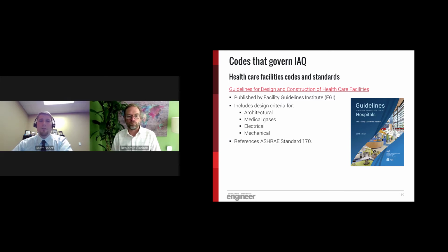Continuing on guidelines that are specific for healthcare facilities, this document is called Guidelines for the Design and Construction of Healthcare Facilities. It's a very important document to be familiar with if you're designing HVAC systems that serve a hospital or healthcare facility. As I mentioned on the previous slide, this document is published by FGI, or the Facility Guidelines Institute. The document not only covers HVAC, but it also has design and construction criteria for architectural, medical gases, and electrical systems. This is a document that is widely used across the country to verify construction and operation of licensed medical facilities. And once again, just wanted to point out that this document does reference ASHRAE Standard 170 as the ventilation standard for healthcare facilities.